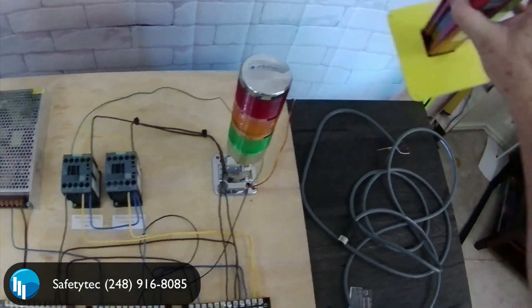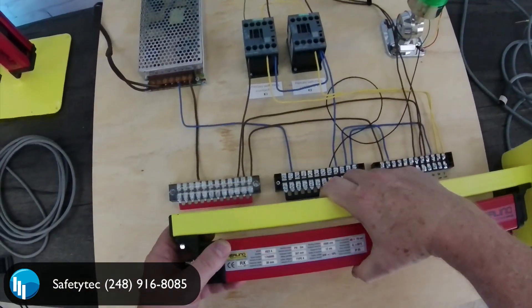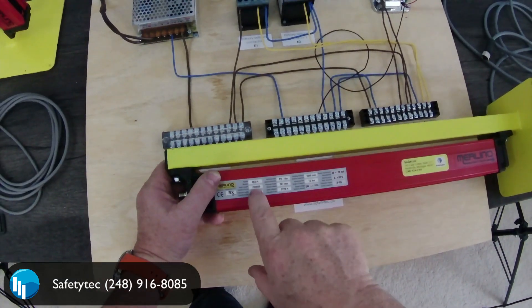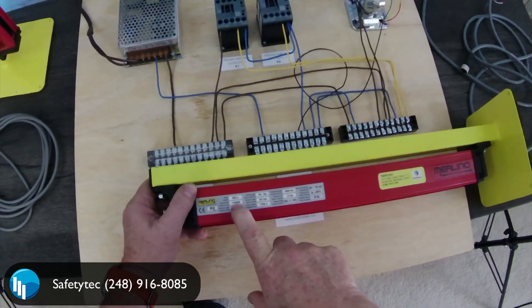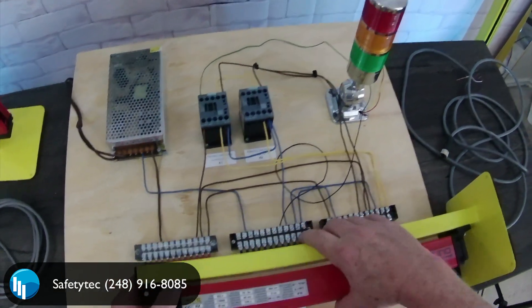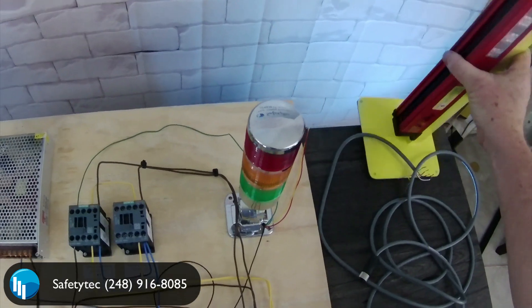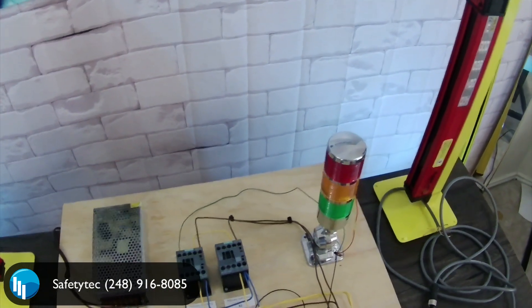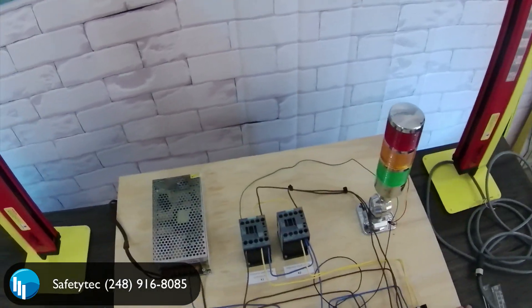Before we get started, it's really important to mention that with all light curtains, you need to make sure that the serial number on the transmitter matches the serial number on the receiver. Very, very important. If they're not a matched pair, it means it's either not a safety guard or it's not going to work.